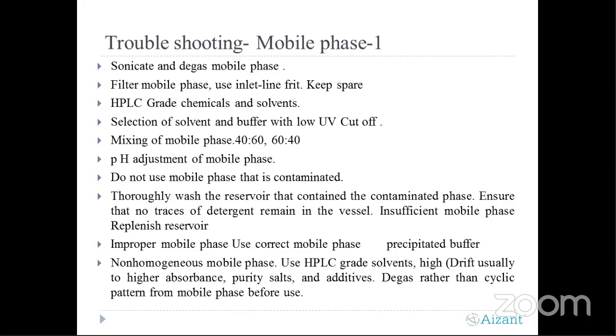pH adjustment also plays a crucial role in the mobile phase. Always try to have a separate pH meter for mobile phase preparation. Don't bring a single pH meter around the lab for multiple purposes; that will challenge your pH adjustment of the mobile phase. If you find your mobile phase contaminated, please do not use it. Now the reservoirs and contaminated phase. In most labs we use normal detergent, and specific reagents are also used for glassware washing. So we have to think very precisely about whether it is clean or not.